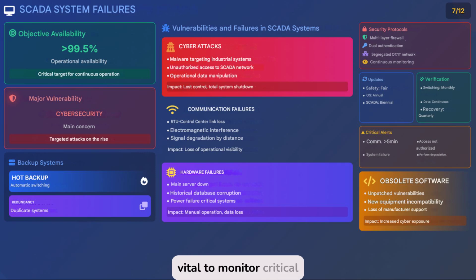It is vital to monitor critical alerts, prolonged communication interruptions, unauthorized access, performance degradation, or system failures. These signals should not be ignored, as they predict major failures with technical and economic consequences. In short, although SCADA systems do not fail frequently, their failure can bring the entire plant to a standstill. Maintaining cybersecurity and keeping these systems up to date is not a luxury, but an essential investment to ensure the continuity, profitability, and sustainability of the power plant.